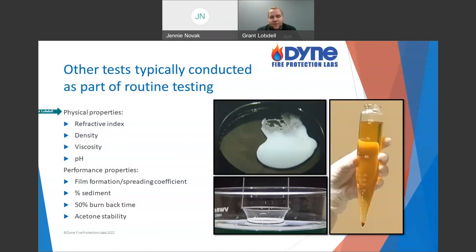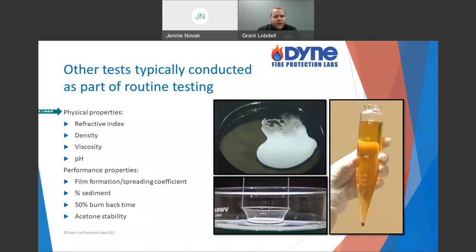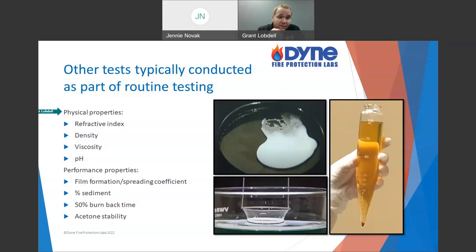Note that viscosity is not done on every foam — at least not here at Dyne. AFFF is very thin, almost like water; it's going to register near zero on our spindle measurement, so we typically don't report that for AFFF. But for anything that's thick — protein foams, AR foams — we'll give you a viscosity measurement.